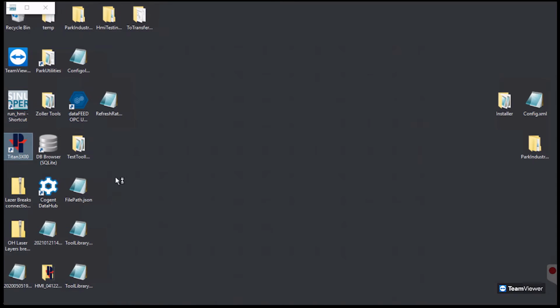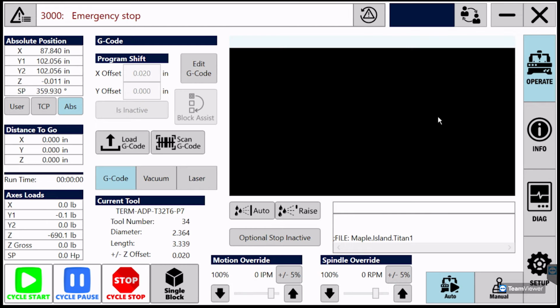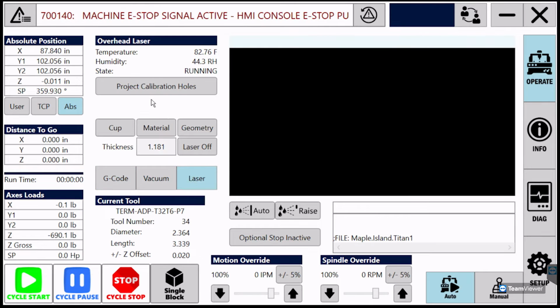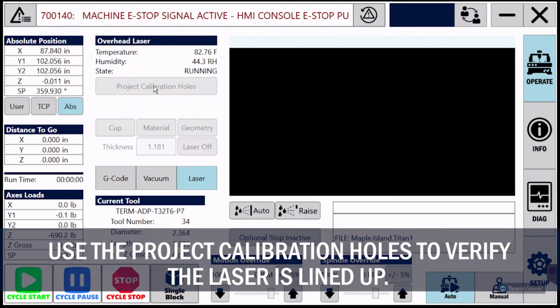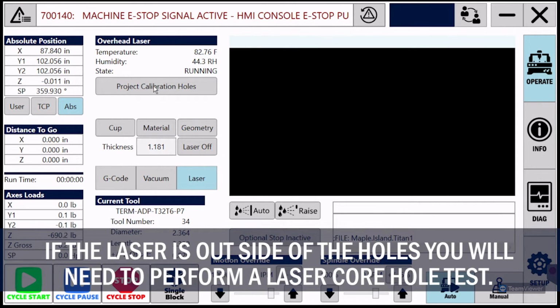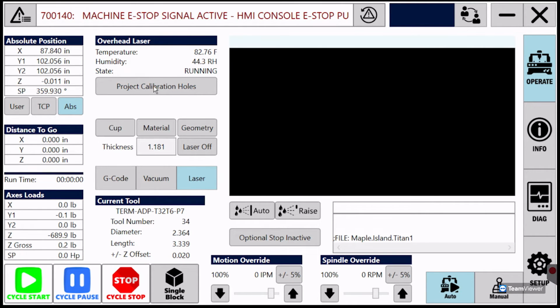Close out of the Z Laser software and open up the Titan software. One last step we'll need to do is project the calibration holes. Double check that your laser is going around the holes. If it's off in one way, we can adjust it using a laser core hole test, which we'll show you next. If they're on and you're happy with the results, you can go ahead and put the machine into service.